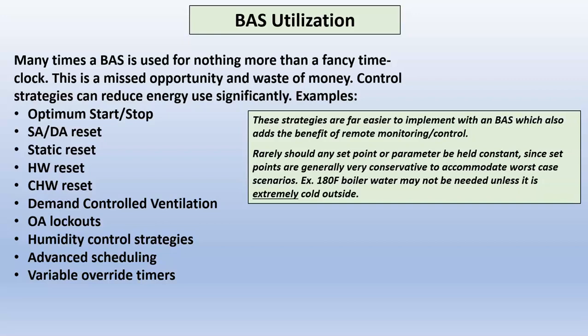Basically, the gist of this is rarely should any point or parameter be held constant if it doesn't have to be. Set points are generally really conservative to accommodate the worst case scenario, like what we talked about on optimal start. So you need to use the BAS to get away from fixed, rigid set points and get into a more variable mindset.